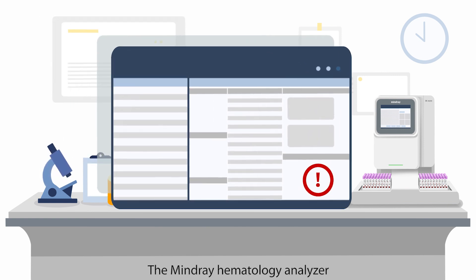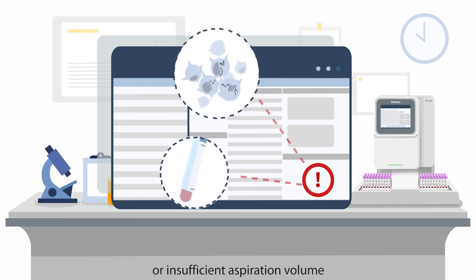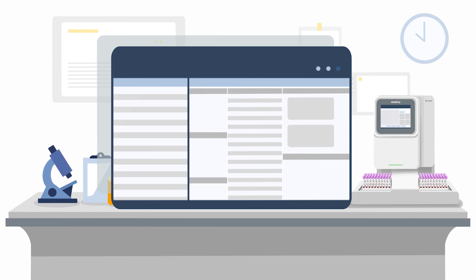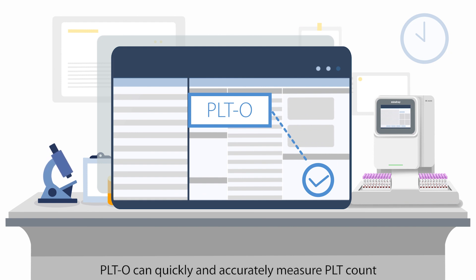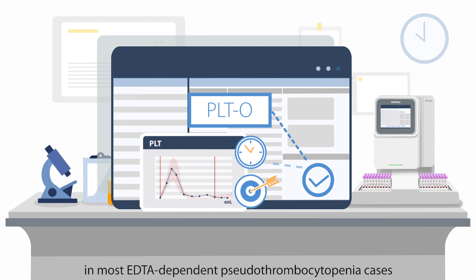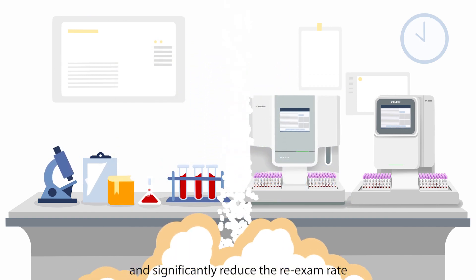The MindRay hematology analyzer can automatically warn of the presence of a blood clot or insufficient aspiration volume. The optical method of MindRay's SF-Cube technology, PLT-O, can quickly and accurately measure PLT count in most EDTA-dependent pseudothrombocytopenia cases and significantly reduce the re-exam rate.